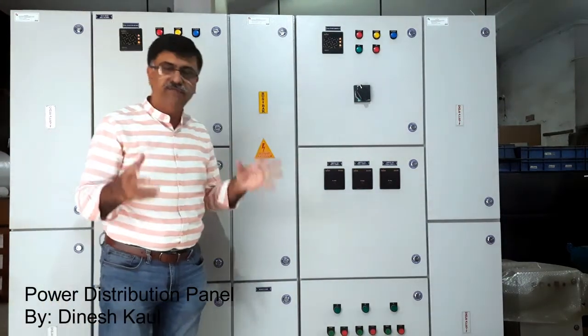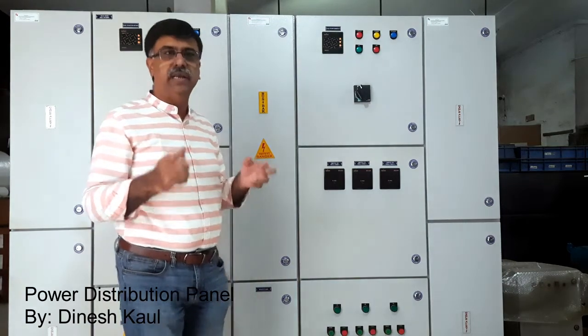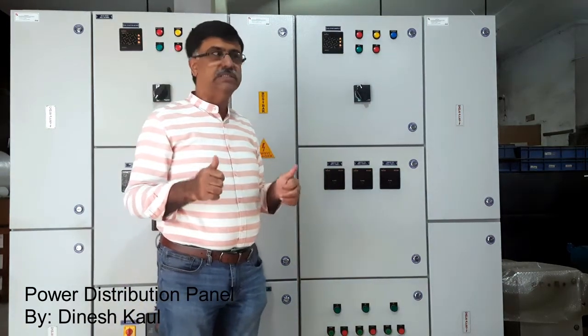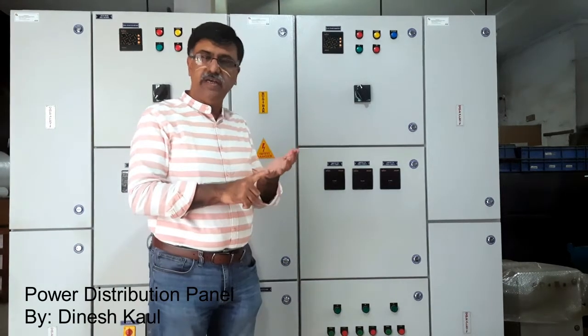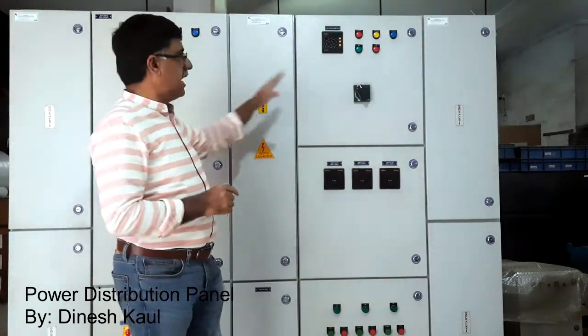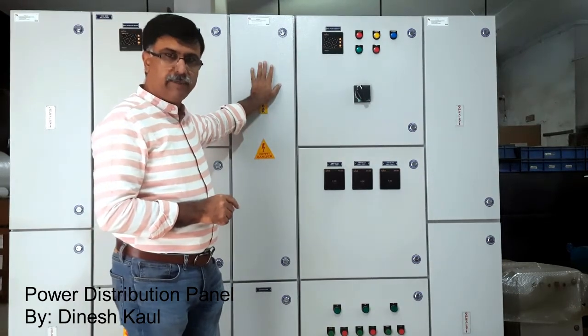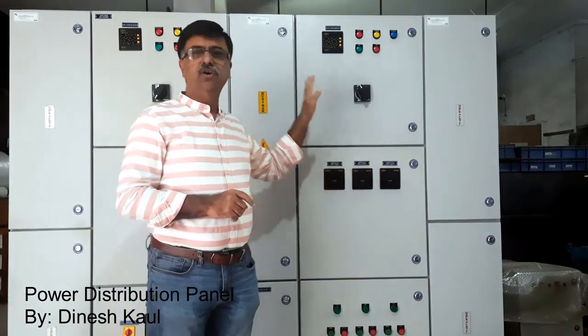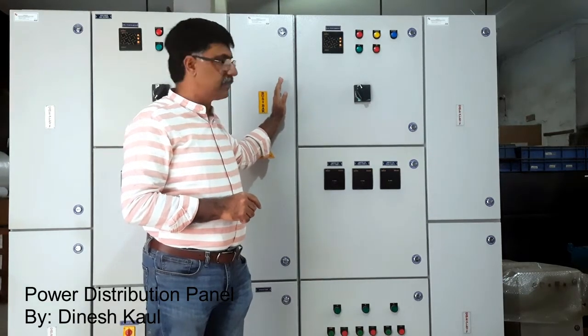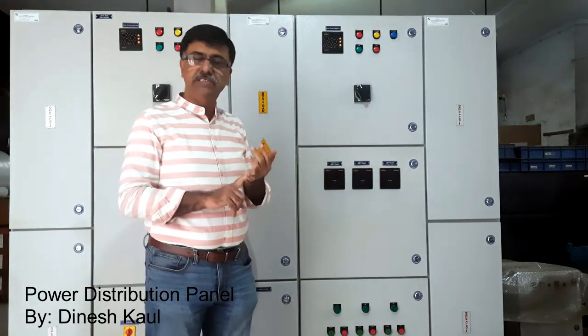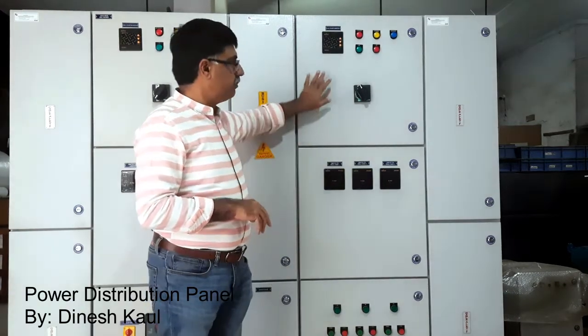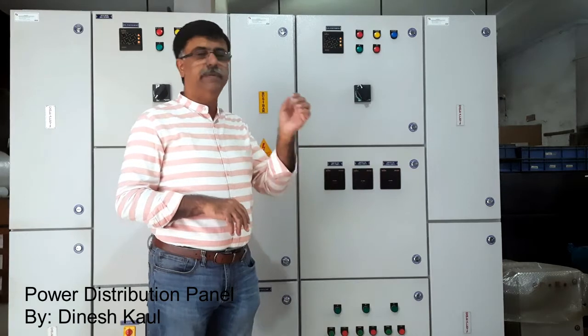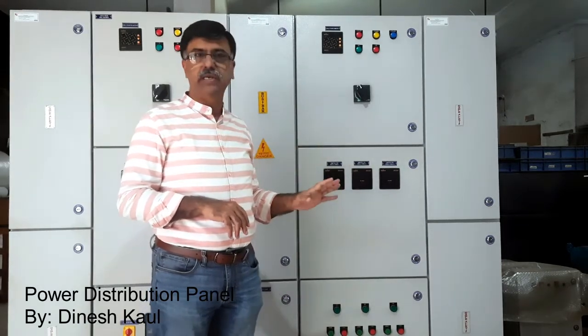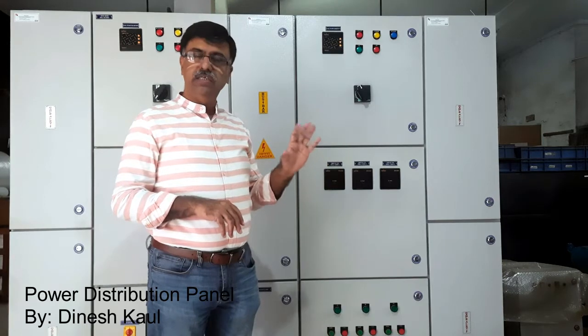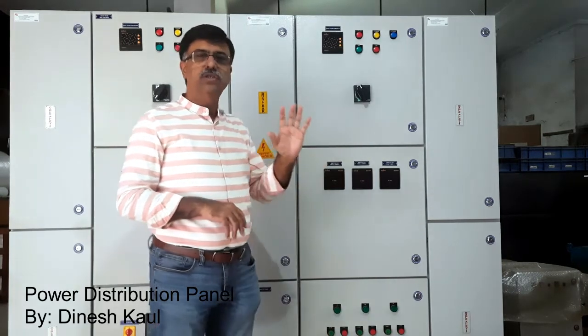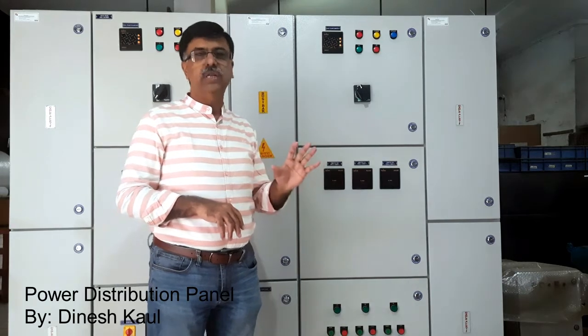So you have a 50 kA rated aluminium bus bar, which is rated for the higher of these two ratings, in this case 400 ampere, with a current density of 1 ampere per mm square. And similarly, it has a temperature rise capability. This box is an IP54 class box, which means normal dust and normal moisture will not get into it and will not destroy this panel. So this is something that will last for a very long time without any problem.